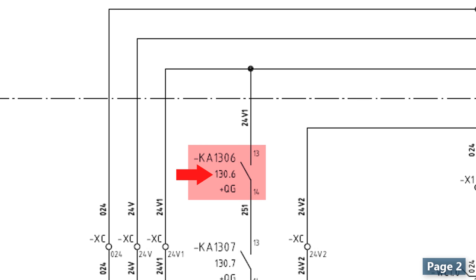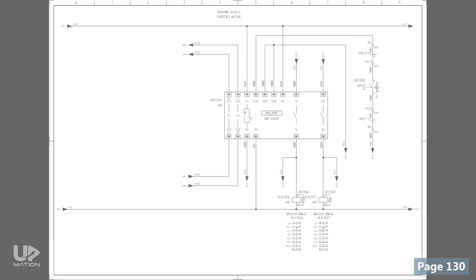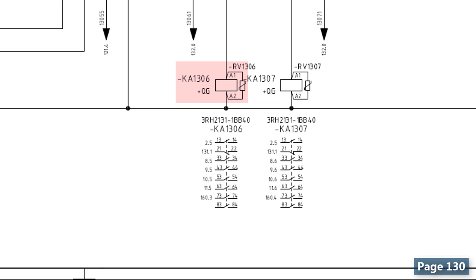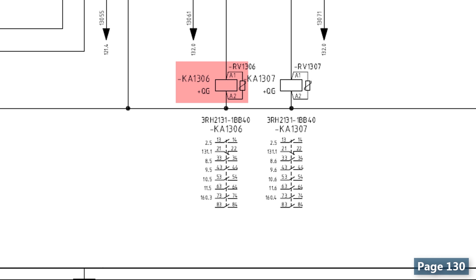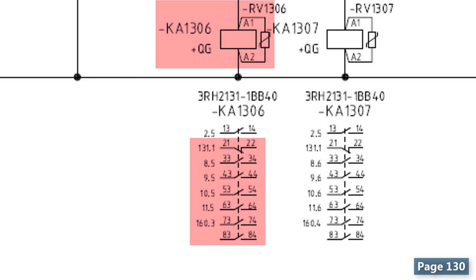As another example, the number below this contact says page number 130 and column number 6. I'll turn to page 130 and this is column number 6. And there it is, the same tag KA1306 as we had expected. It looks like a coil, but not the coil of a contactor, the coil of a relay. And how do I know that? If you have seen the legend and abbreviation page of the drawing, you know that the KA is a nomenclature for a relay in this drawing. Below the coil, you see the 13-14 contact of page 2 and also the other NO and NC contacts of this relay with the addresses they have been used in this drawing. We'll come back to this page very soon.